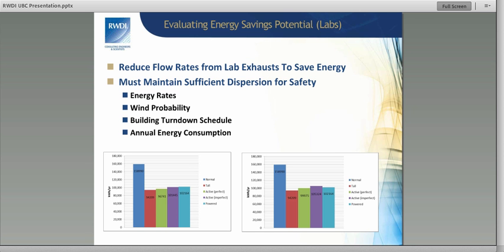If we've got a contamination issue that's been shown through the wind tunnel tests, yeah, maybe we do. But maybe we don't. Maybe we want to show that we can actually pull that flow rate down, use less energy, use less air. And when you use less air, what happens? Your exit speed from that stack comes down. We're no longer necessarily able to escape these wake regions on the roof, and you increase your possibility for contamination. Well, that's something we want to avoid.